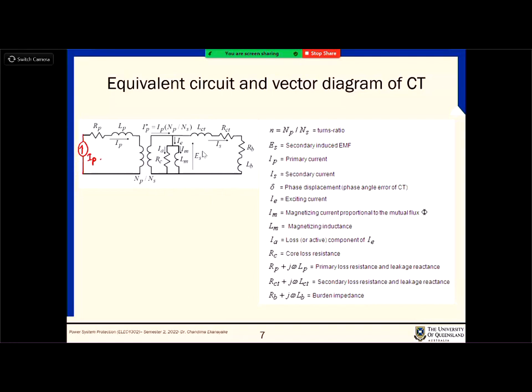You can see that the center branch is called the magnetization branch, and then this is the load branch, where the RB and LB are the impedance coming from the relays, and then this part is coming from wires and also the CT inductance and CT resistance. And if you have a wire resistance, you can add it here as well. Okay, so usually we represent all these things on the secondary side of the circuit, because on the primary side we keep it as just a current source supplying a certain amount of current that is going through the primary winding.